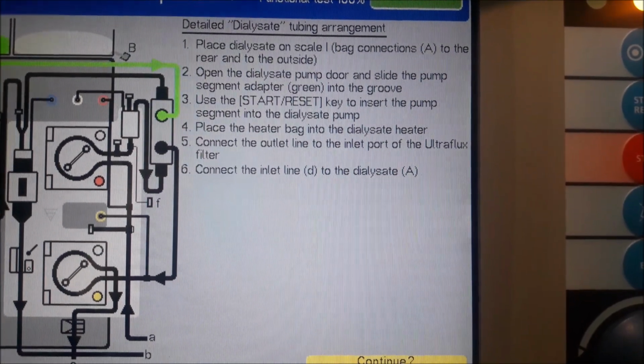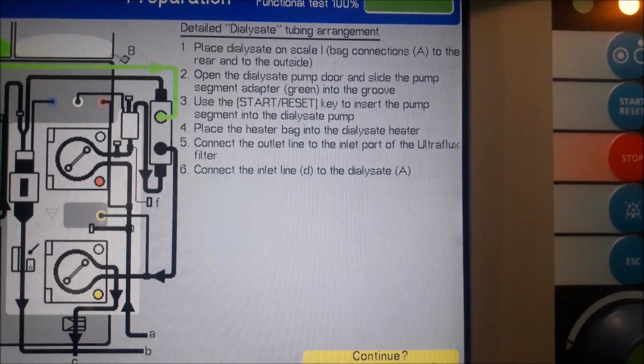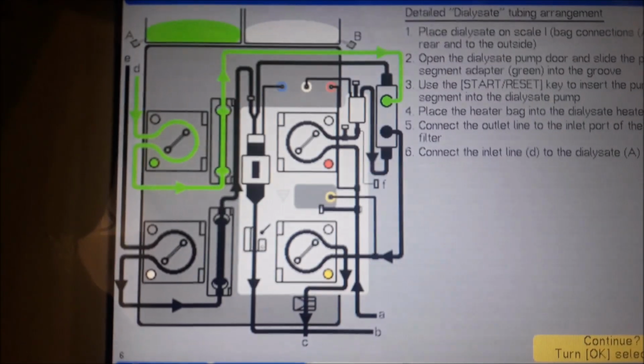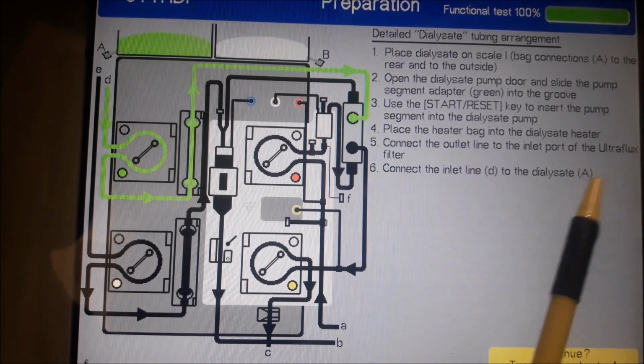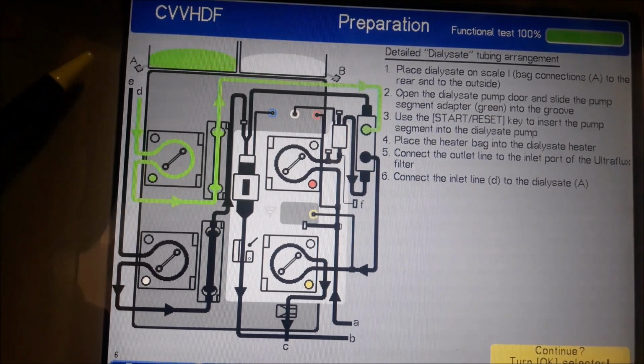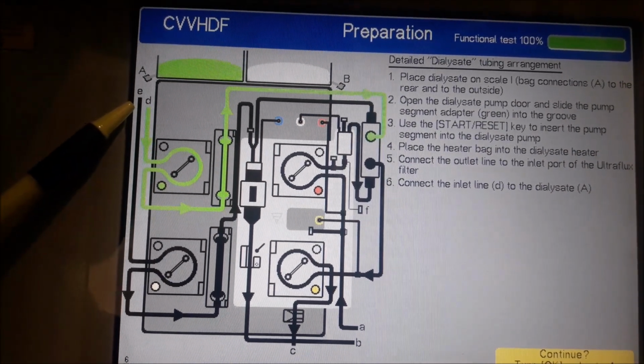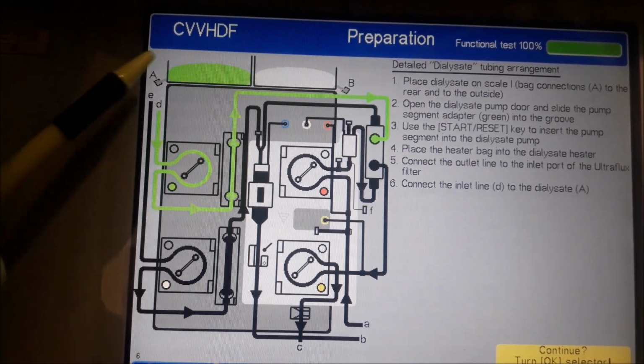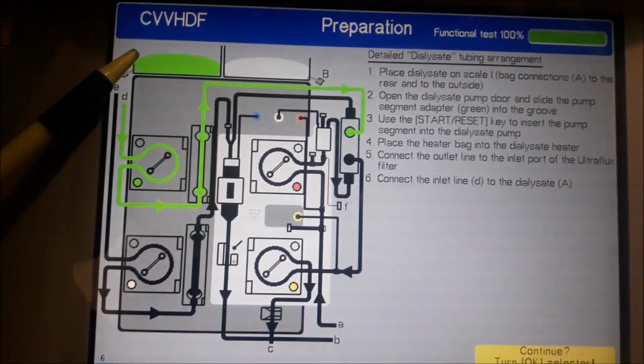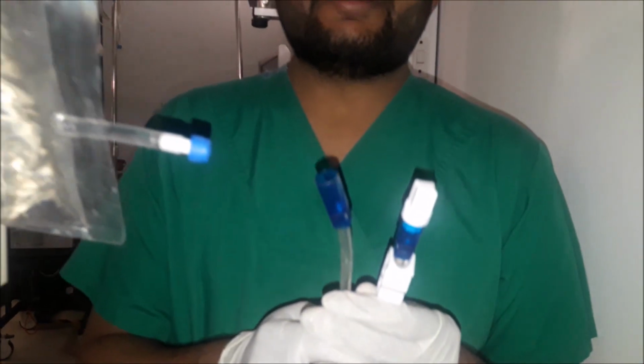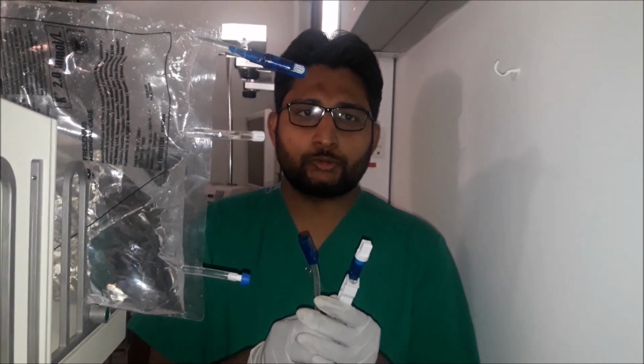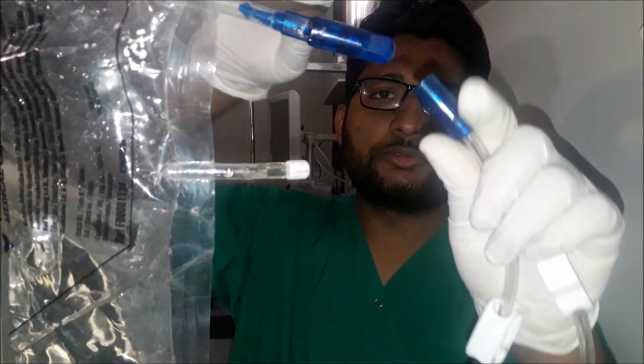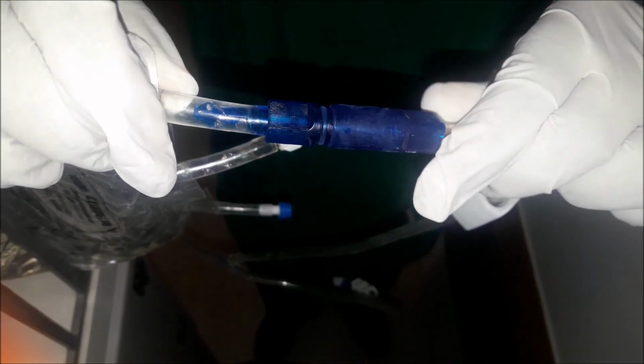Point number 6. Connect the inlet line D to the dialysate A. Let's find the line D and dialysate A. In this picture, you can see the D line is coming from the pump and the A line is coming out from the dialysate. Guys, now I am at the back side of the machine. Here I have the two ends which are coming from the dialysate tubing. One end will attach to the dialysate fluid like this. Now the tubing is attached to the dialysate fluid.